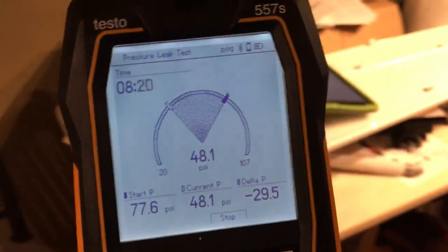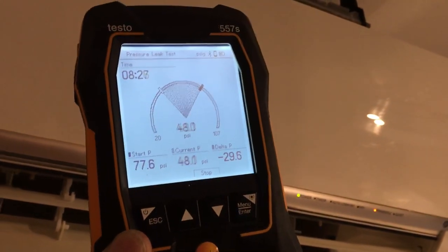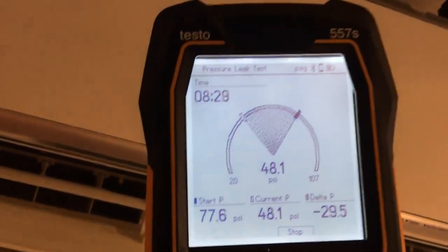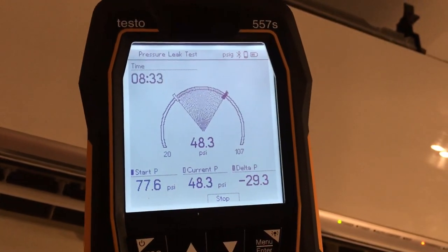Okay, so there's the pressure, 48 PSI now and falling. So now let's get it up by the hot air. So this is the pressure test mode. So now you see it going back up.